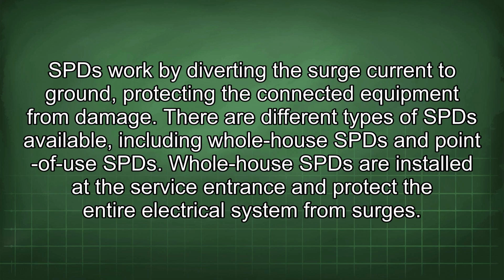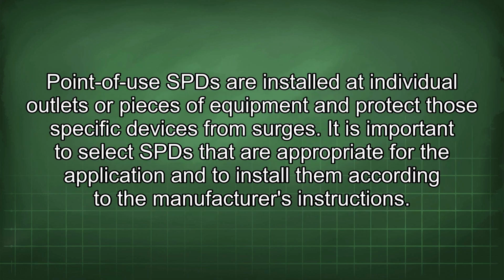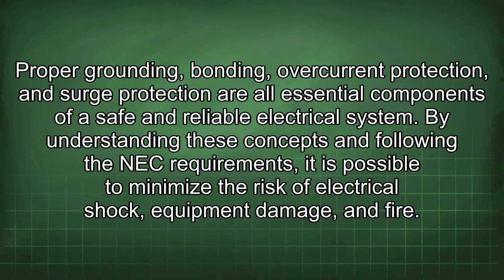There are different types of SPDs available, including whole house SPDs and point of use SPDs. Whole house SPDs are installed at the service entrance and protect the entire electrical system from surges. Point of use SPDs are installed at individual outlets or pieces of equipment and protect those specific devices from surges. It is important to select SPDs that are appropriate for the application and to install them according to the manufacturer's instructions. Proper grounding, bonding, overcurrent protection, and surge protection are all essential components of a safe and reliable electrical system.